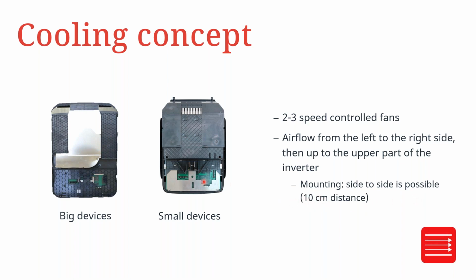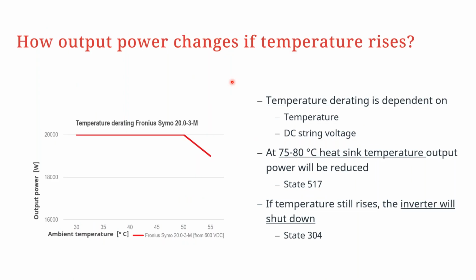As far as mounting is concerned, for this to be efficiently done as far as cooling is concerned, we do require a minimum distance of at least 10 centimeters between inverters. So it's important also to take care of these considerations. When you look at an actively cooled inverter, it gives you the benefit that the derating due to temperature is going to be at a much later stage, as we can see in this curve. Considering an inverter like a Symo 20 kilowatt inverter that has a capacity to deliver 20 kilowatt, and this being our ambient temperature on this scale, we can operate the inverter up to about 50 degrees ambient temperature when the input voltage of the DC side is about 600 volts before derating of power begins.